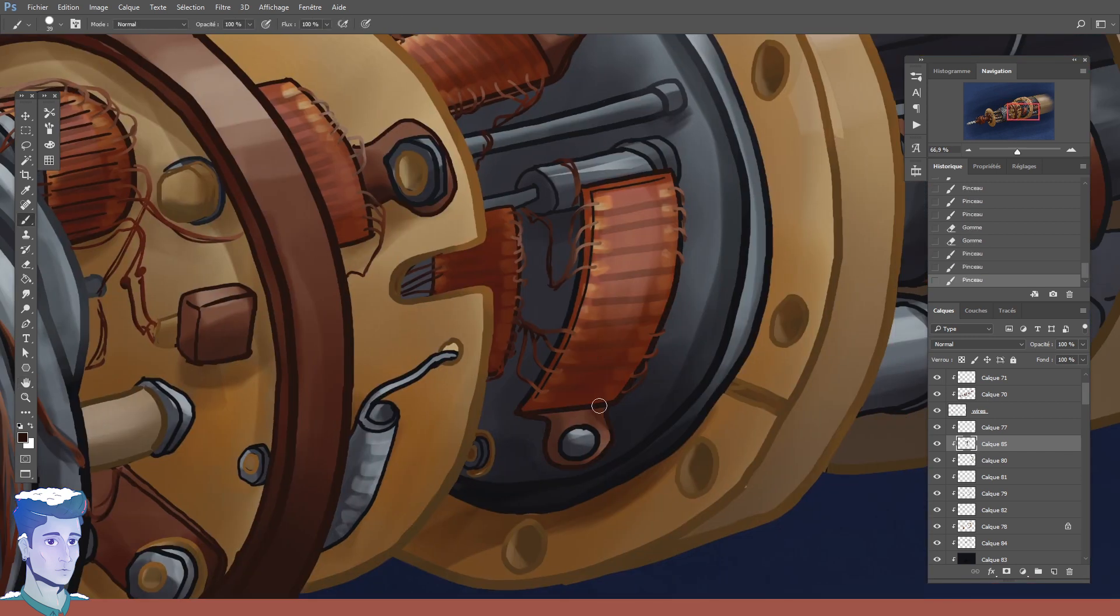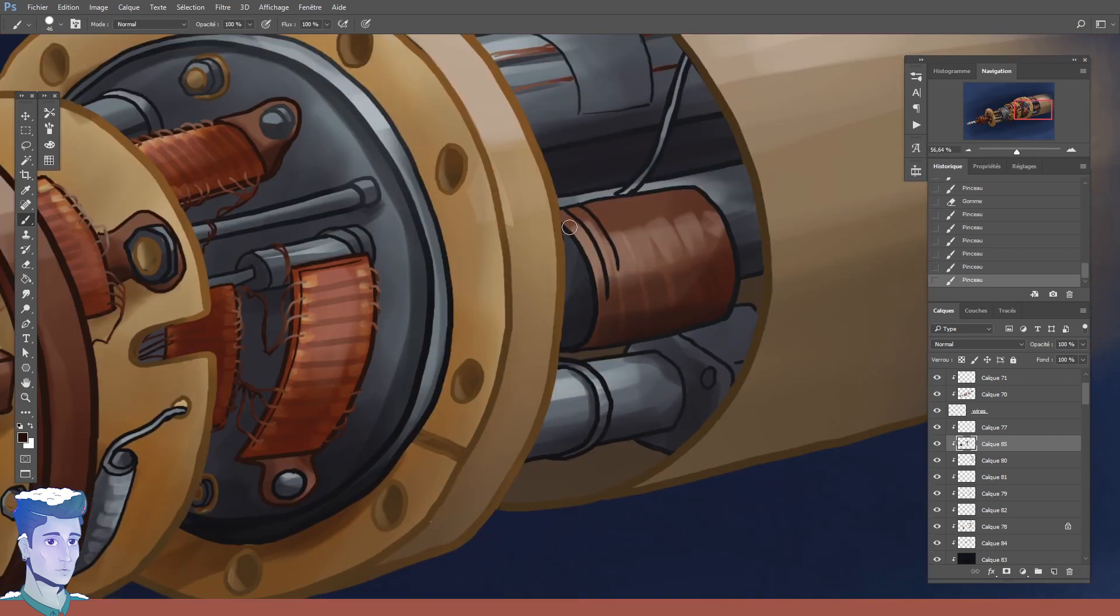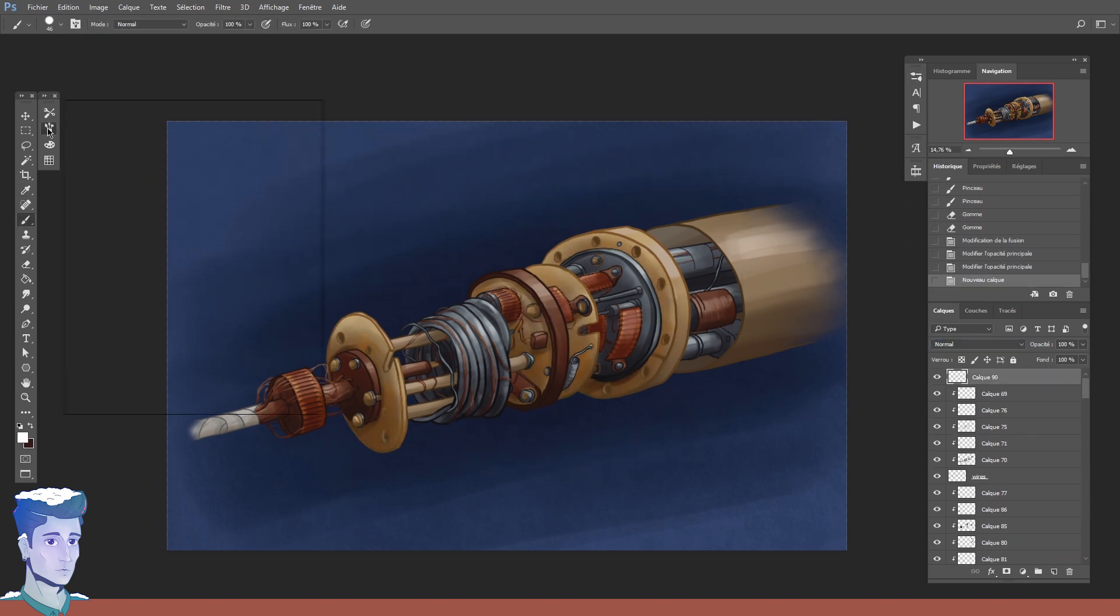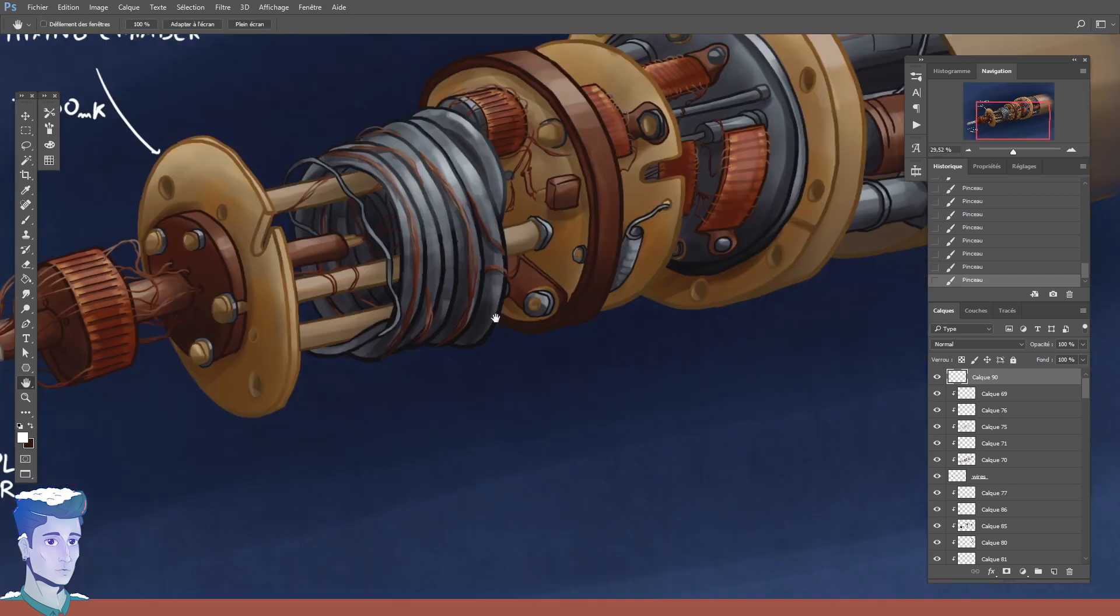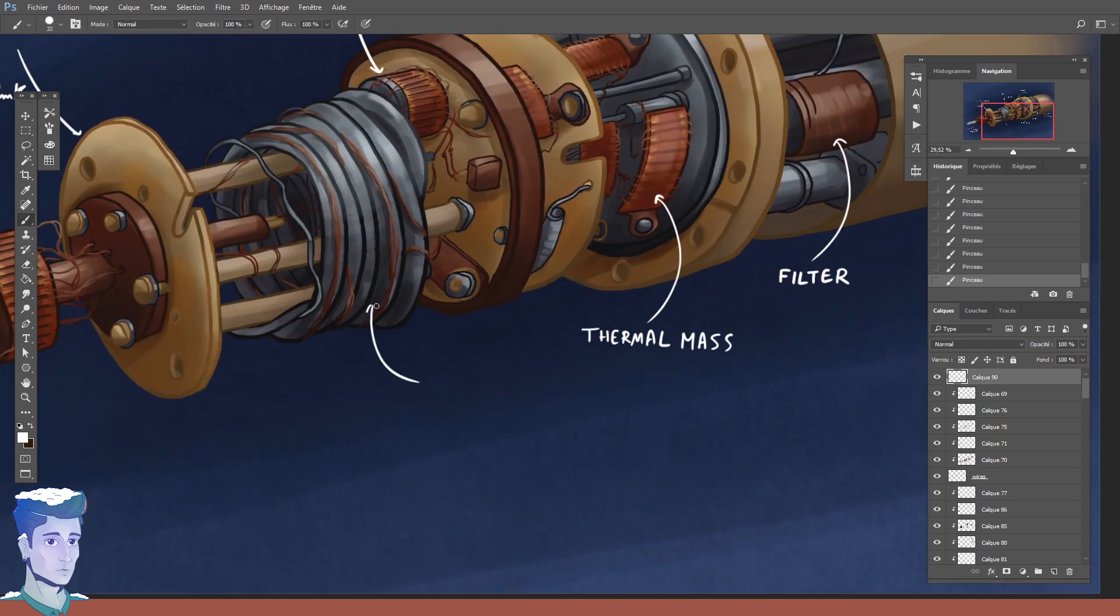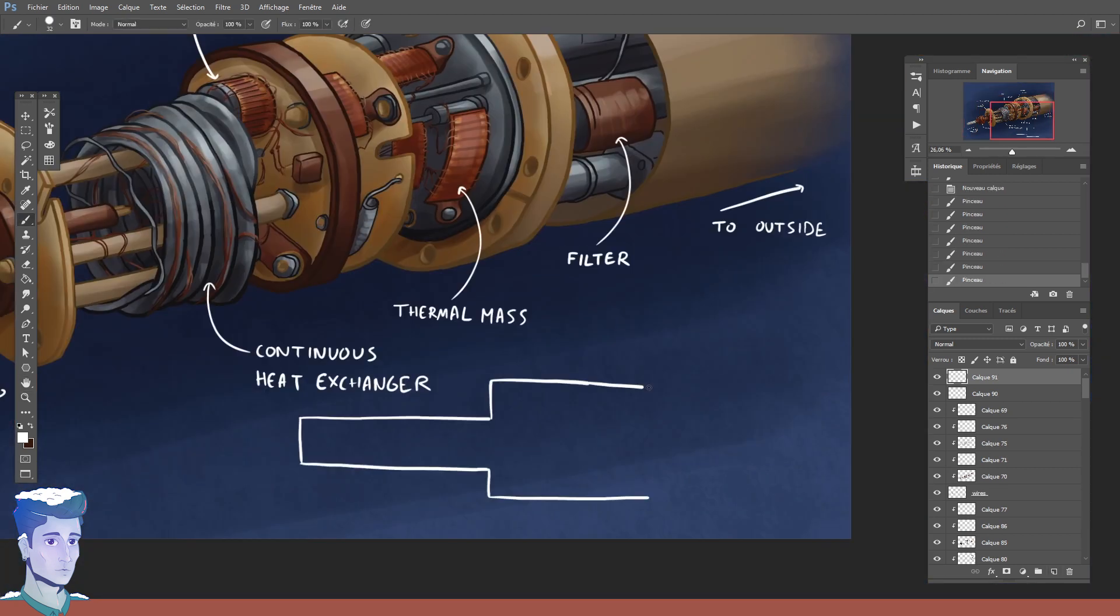Because my setup is fully experimental and homemade, over the last three years I made a lot of repairs on this dilution fridge. Now I know it by heart. I replaced a lot of parts, I changed the wiring a couple times. Some of the wires I drew at the end are made of copper. Others are superconducting to avoid heating. I think this setup has about 140 pieces of wire of different length, glued or taped with special materials in various parts to cool them, and soldered on gold-plated tracks at various points. It has 8 thermometers to ensure all the stages are functioning properly and so on. Heating elements too for when you need to put the setup back to room temperature.